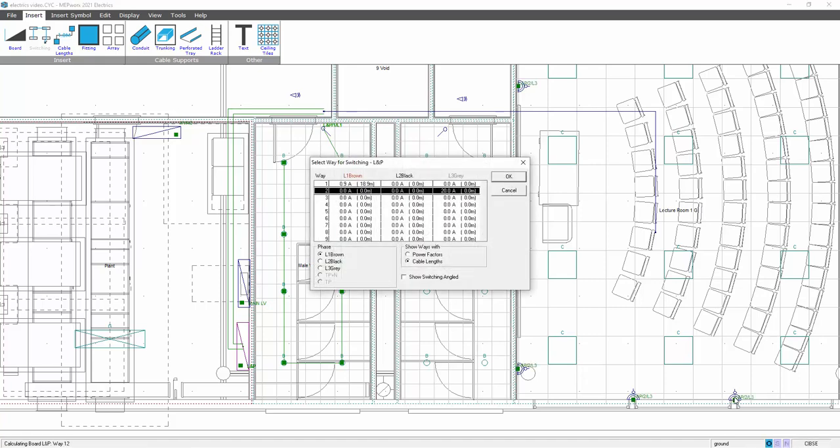I then click once on each socket. Double-click to complete the circuit. That basically tells the program to finish that particular run, and that provisionally gives you a 20-amp load on that circuit. Now later on in the wiring program, you can say it's 32-amp ring main, it's got RCDs and all the rest of it. All of that is done in the wiring program. You just get a provisional load of 20-amps here, because likely it's not in this, it might be a radial.